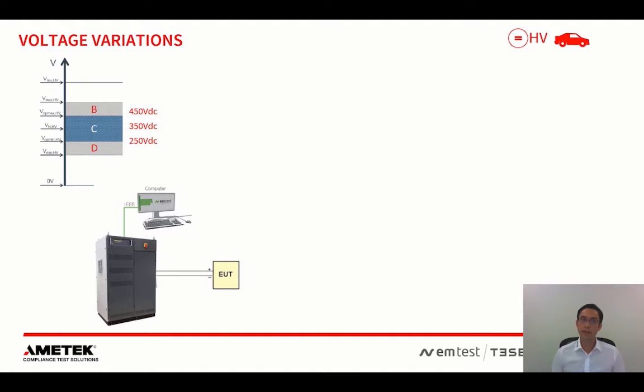So the first test we're going to look at is the voltage variations. So voltage variations tests the immunity of a high voltage component when it is operated or supplied by different operating voltages. On the left, you see an example. So the nominal voltage of that component is 350 volt DC. Now the blue range shows the range where it should operate normally, so in operating status 1. Then it has the range B, which is the over voltage range, and a range D with an under voltage range. And the top line there is the limit, so it's the over voltage limit, and above that limit the component might break, might fail, might not work properly, so it is like a non-defined state.